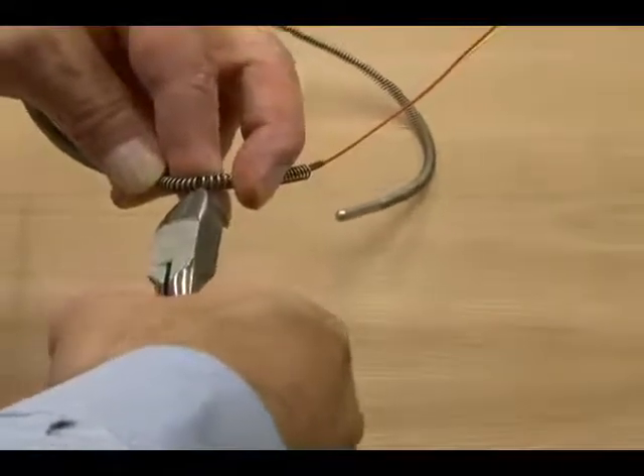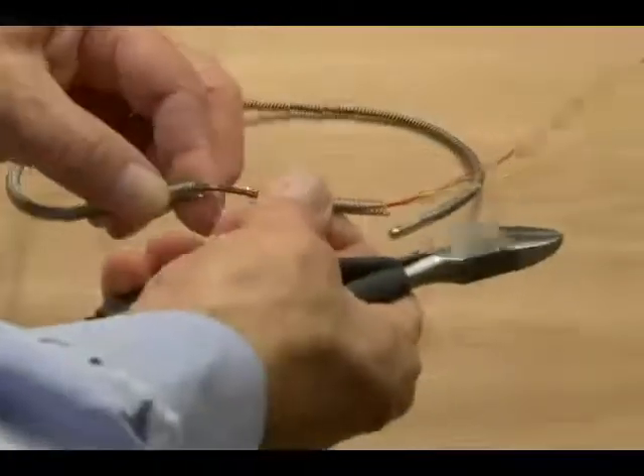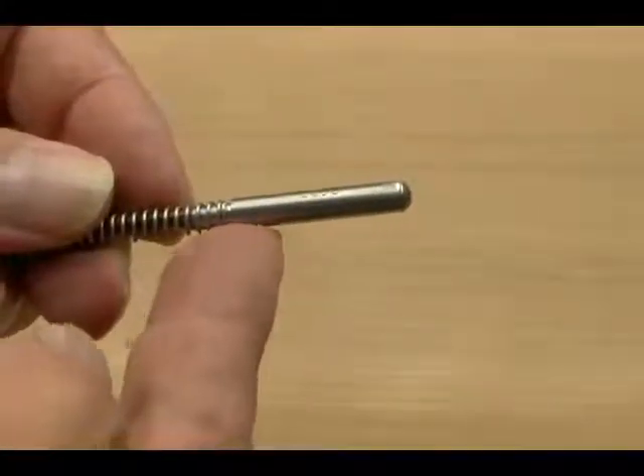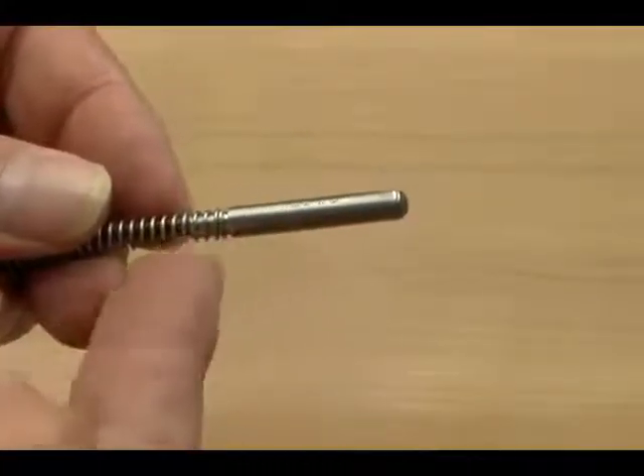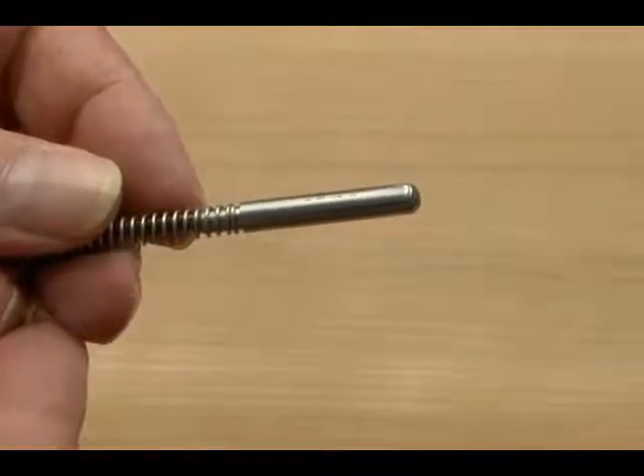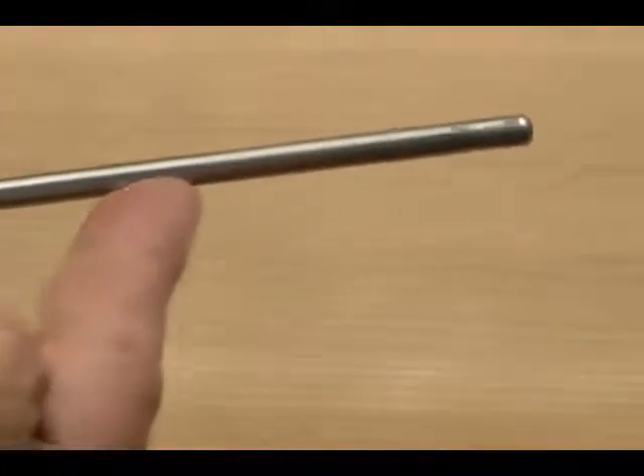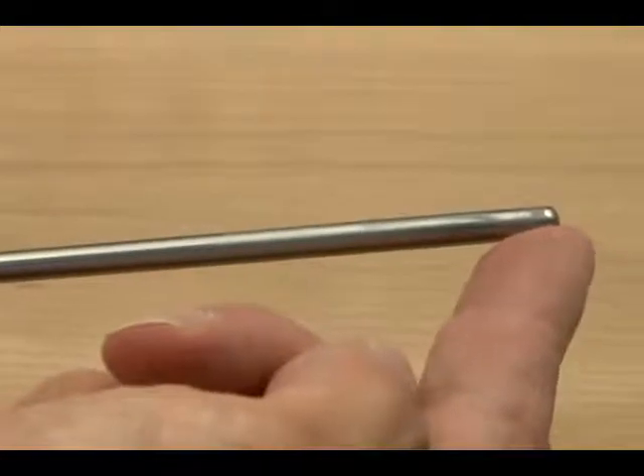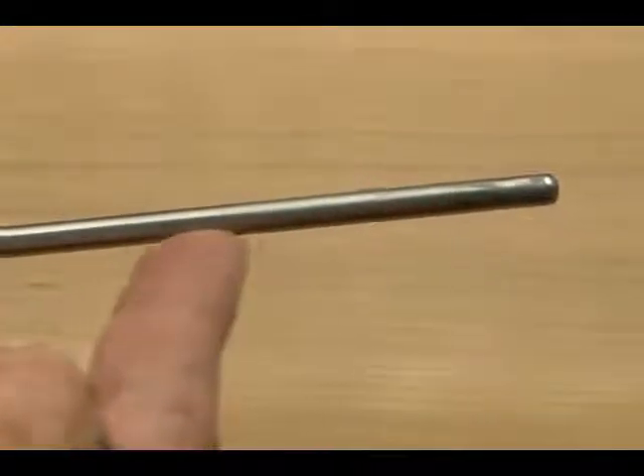You no longer have to stock a variety of lengths of sensors. The worm is one size fits all. Third, the amount of metal surrounding the sensor is reduced, so it doesn't take as long to reach the full process temperature. This means a worm has 13% faster response than a full sheath probe.